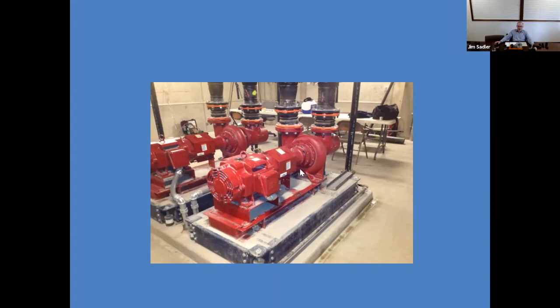And the base is there for rigidity, not for inertia. We often call it an inertia base, but in the case of the pump support, you can't support a pump directly. The pump frame is not designed to be point loaded. And the pump frame will rack if you do that, and you'll wear out the couplings. So the base provides rigidity, and then that frame can then be point supported on isolators.